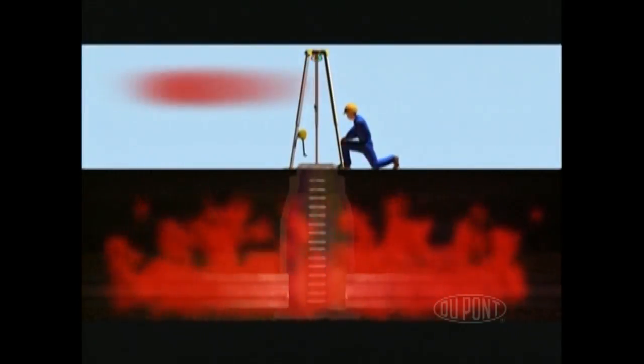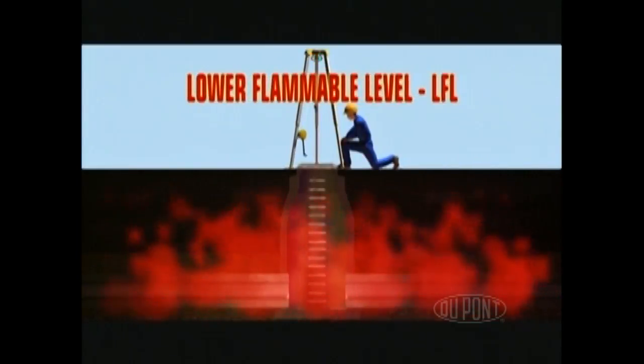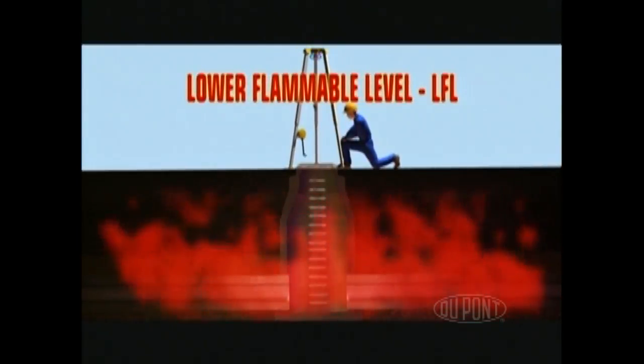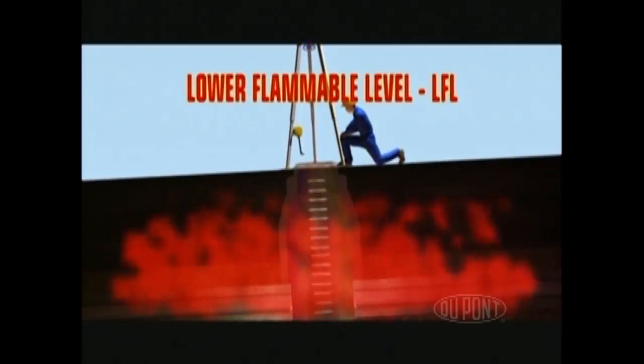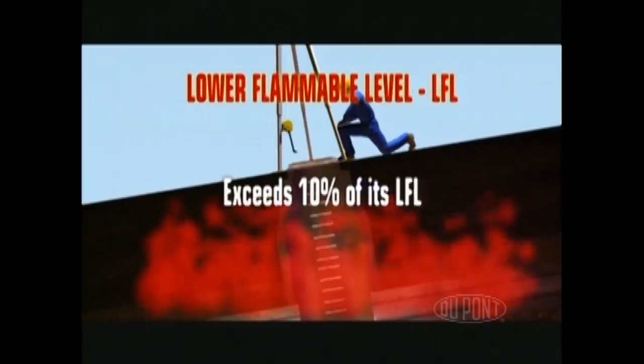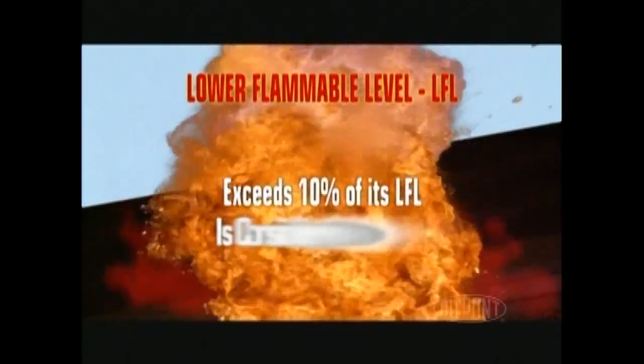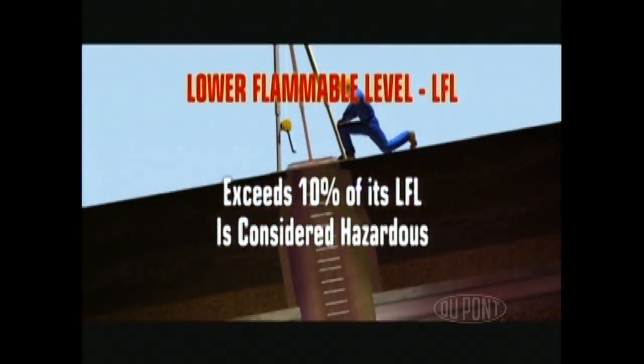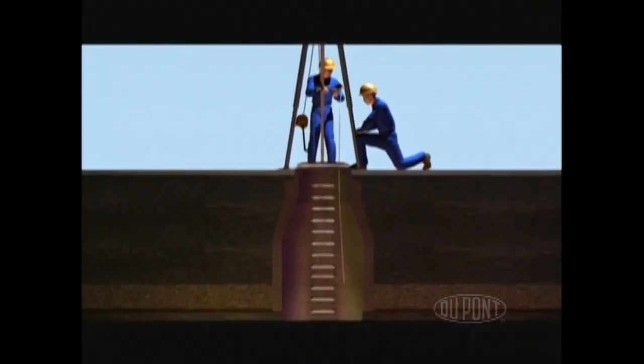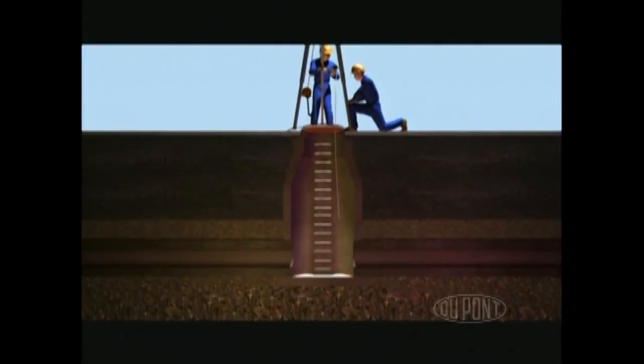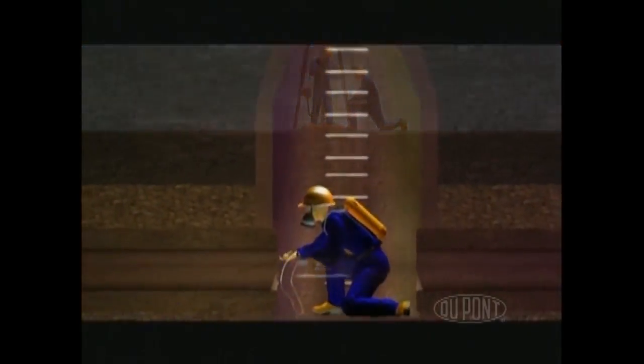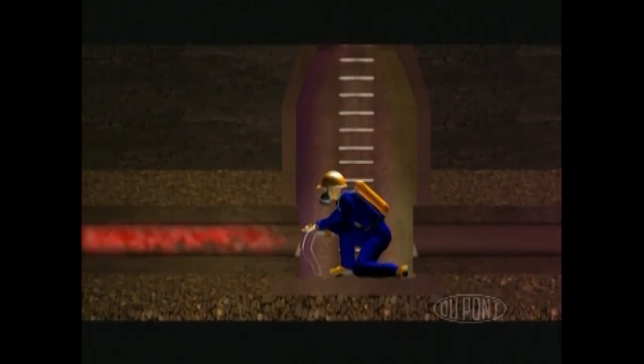A flammable gas's lower flammable level, or LFL, is the amount required for an explosion to occur in normal air. If the level of a combustible gas exceeds 10% of its LFL, or if a combustible dust meets or exceeds its LFL, the atmosphere is considered hazardous and must be purged and ventilated. Be sure to test for flammable gases throughout the space, covering horizontal areas as well. This is necessary because small pockets of flammable gas can ignite if surrounded by non-flammable gas.